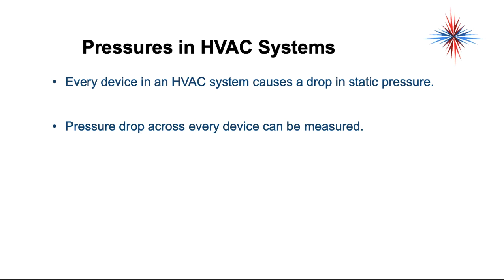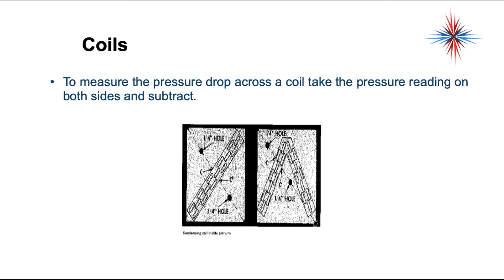Every device in an HVAC system causes a pressure drop — a drop in static pressure. Every pressure drop across every device can be measured. Filters, A-coils, heat exchangers, bends in ductwork, dampers — every device in the airstream causes a drop in static pressure. To measure the pressure drop across a coil, take pressure readings on both sides and subtract the two. That gives you your pressure drop. To take a pressure drop across anything, take a reading on one side, take a reading on the other side, and subtract the two numbers.